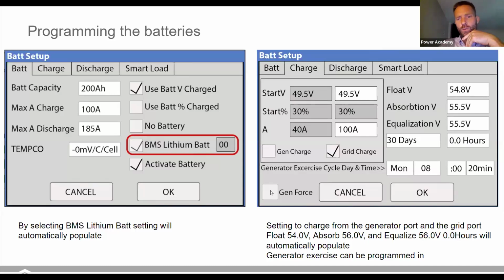If you check this generator force gen, that gen force will just automatically start the generator up. So if you're doing an installation, you want to make sure that, hey, I've got my 2-wire start wired properly, it's going to work. Click this, click OK, that'll start your generator up. Uncheck the box, click OK again, and that will stop the generator. One important thing to keep in mind, if you change settings in a Sol-Ark, you have to click OK. Think of that as the save button. Otherwise, it doesn't change your settings.